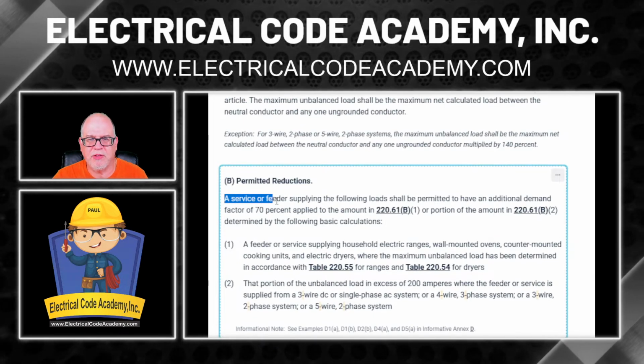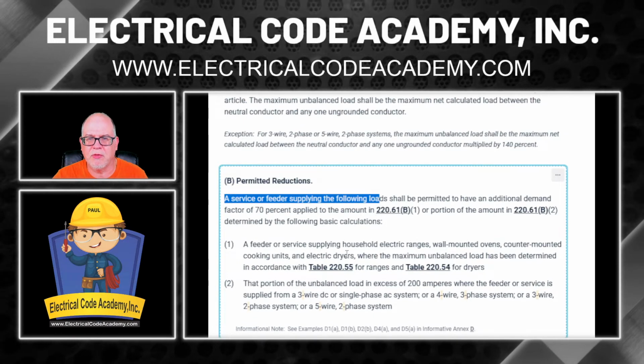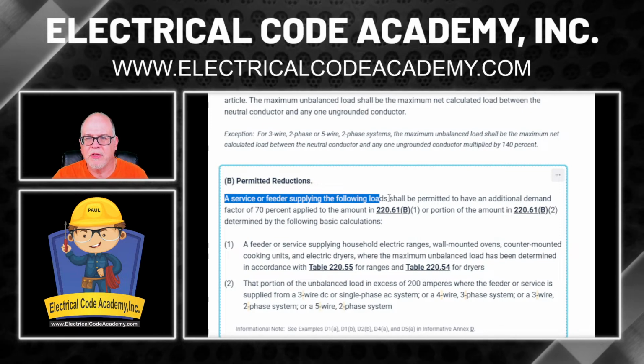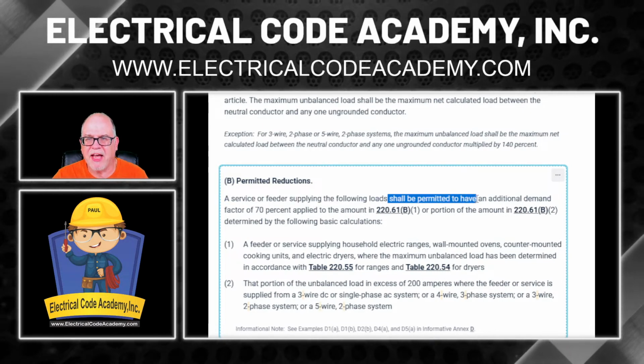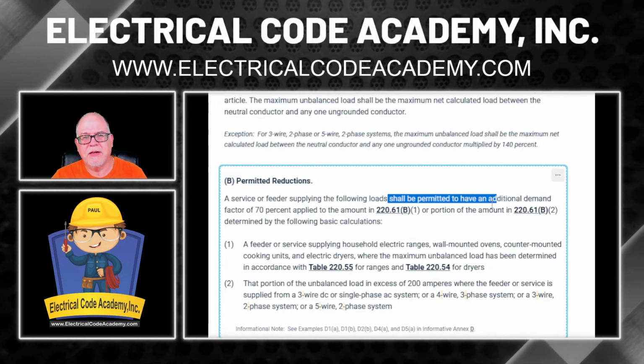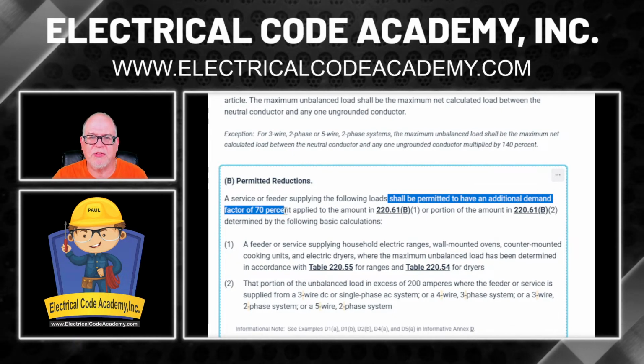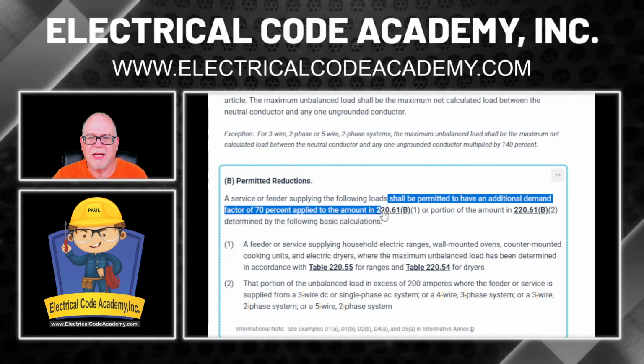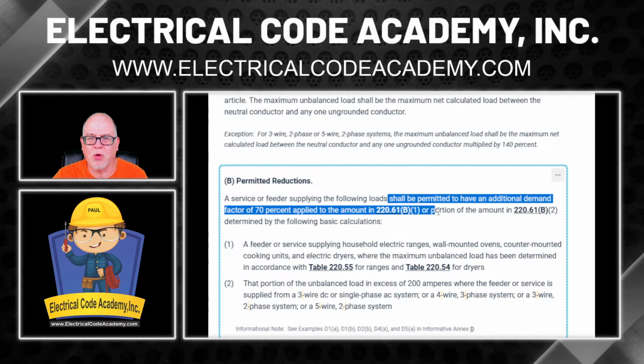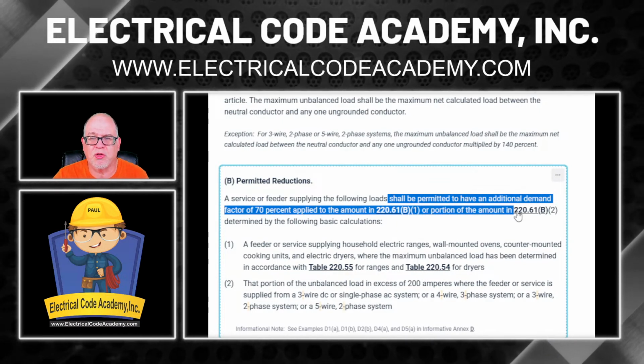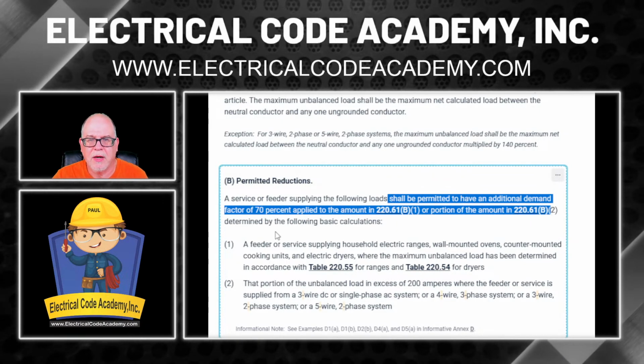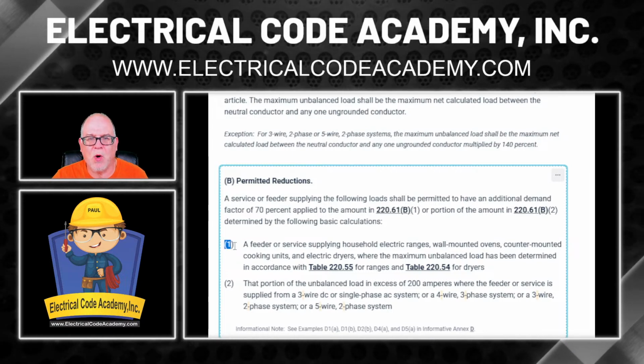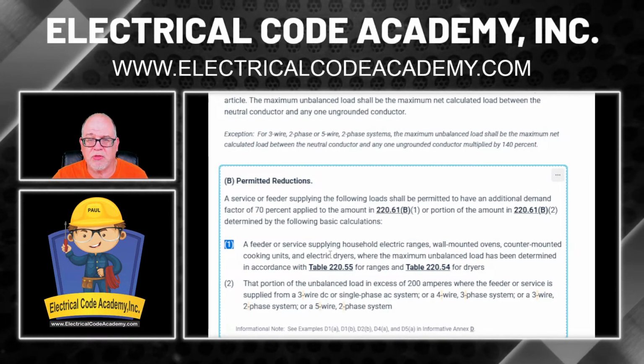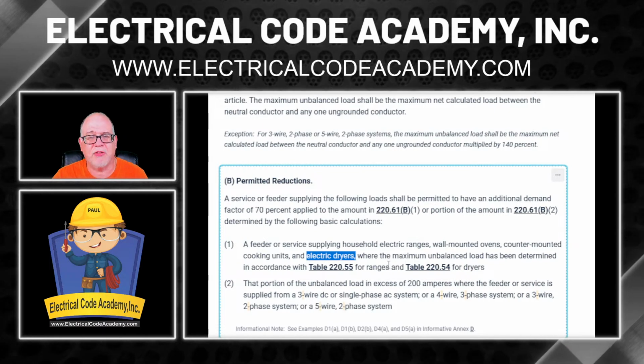It says a service or feeder supplying the following loads, that's these loads right here, shall be permitted to have an additional demand factor of 70% applied to the amount in 220.61(B)(1) or a portion of the amount in 220.61(B)(2). All right. Well, we're going to be doing (B)(1) because, as you'll notice right here, electric dryers are in here.